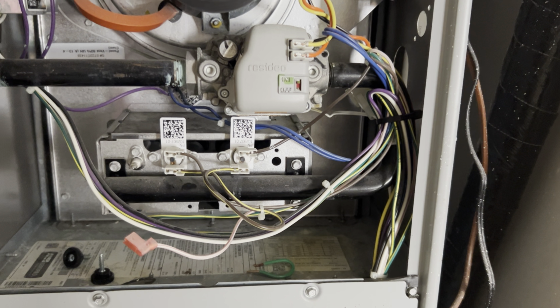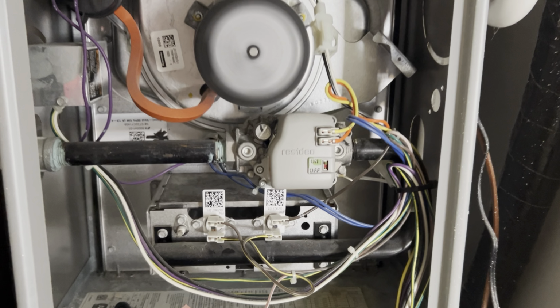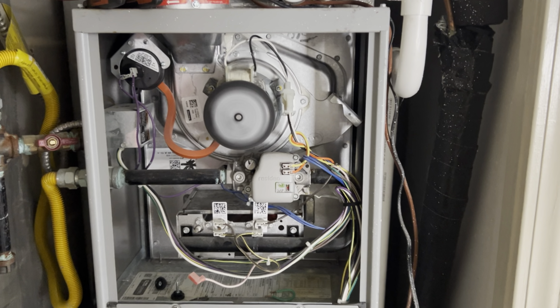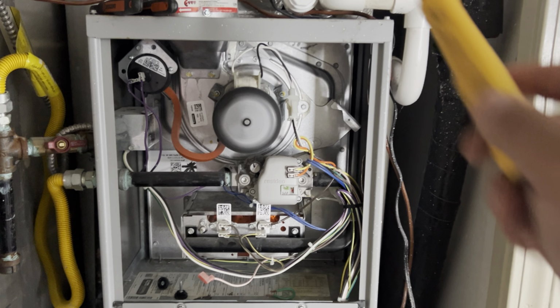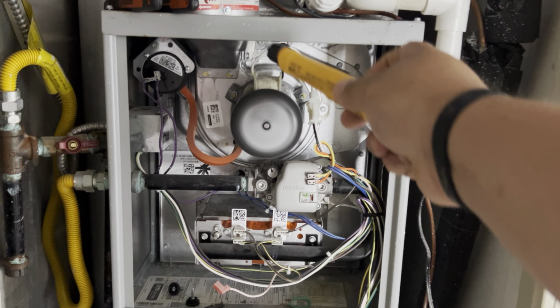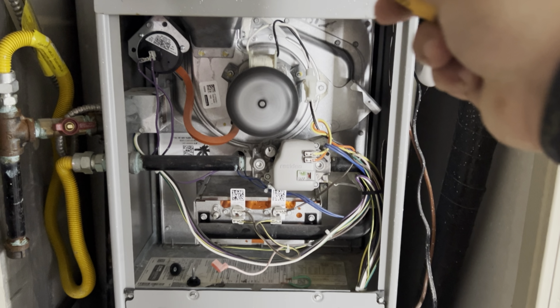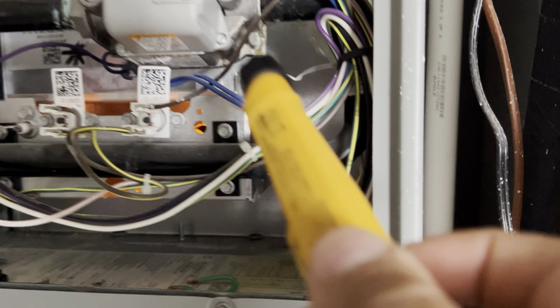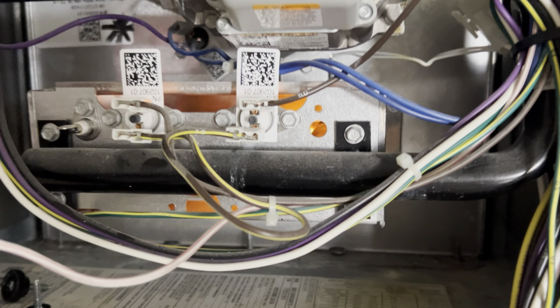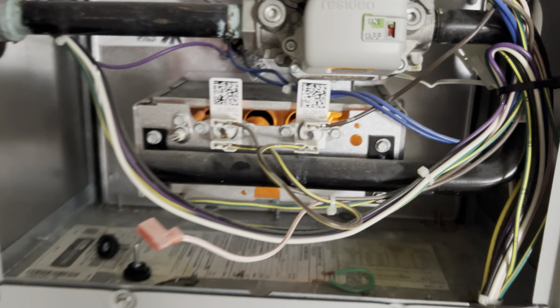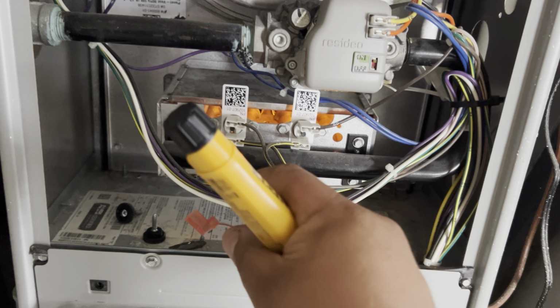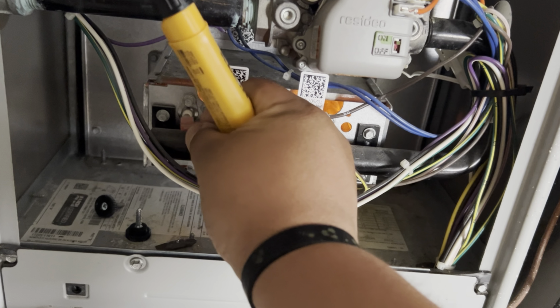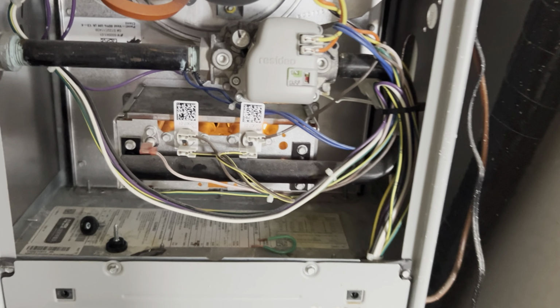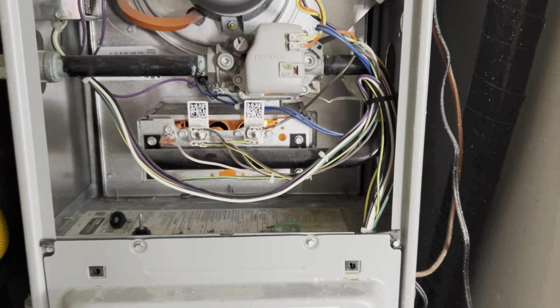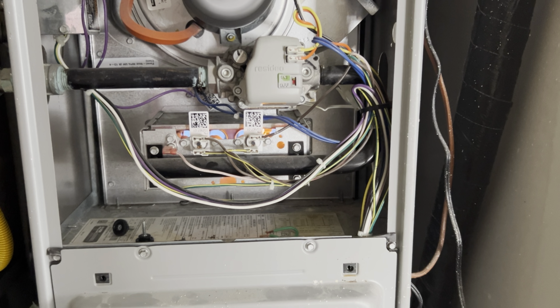In order to diagnose a furnace, it's very important to get the order of operation or the sequence of operation. First, the inducer fan motor starts up and proves airflow by this negative pressure switch. Then the igniter will glow bright cherry red before cycling on the gas valve. When the gas valve finally does cycle on, you're looking for a bright blue flame. If there's any specks of yellow or orange, it indicates a dirty flame.